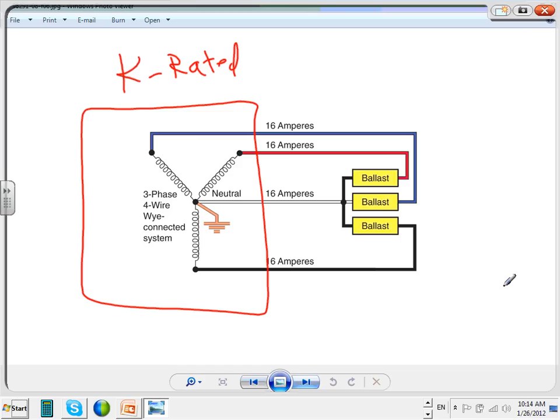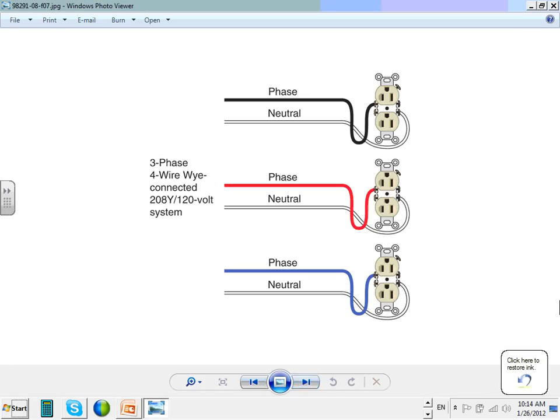So we talked about this one. That resulted from nonlinear loads. So most of the time, guys, if you look at the 16 and 16 and 16 here, this should be 0, right? But it's not, because of the harmonics. They add up at the neutral. Third harmonics add up. Okay, so how do you solve the problem?